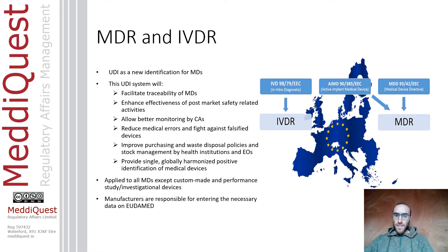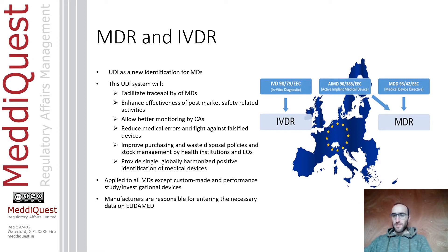Manufacturers are responsible for entering the necessary data on EUDAMED, a new database required by MDR and IVDR, where you should register your company and products. This includes the UDI database and keeping it up to date.